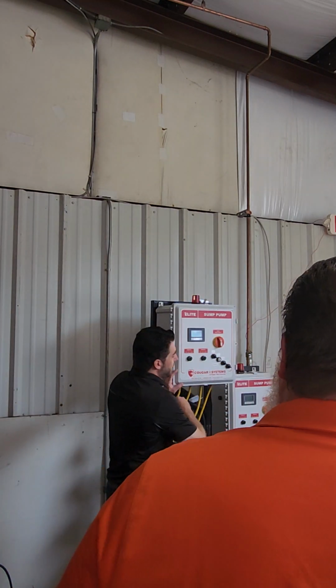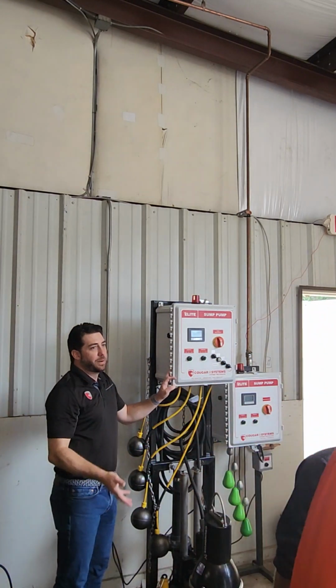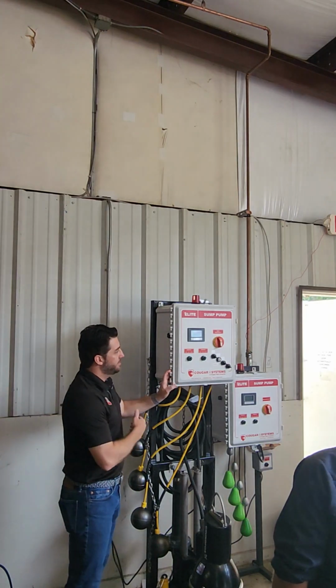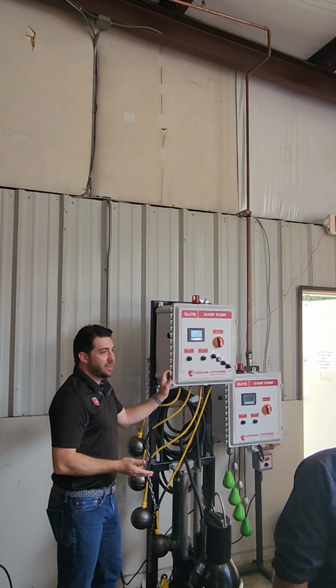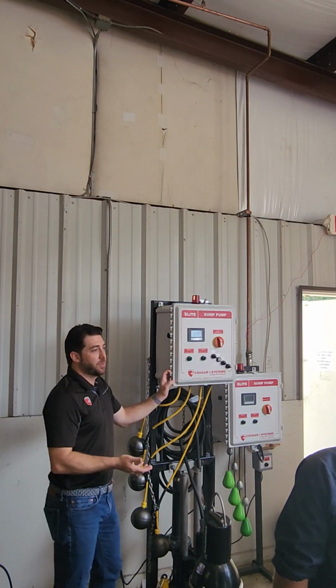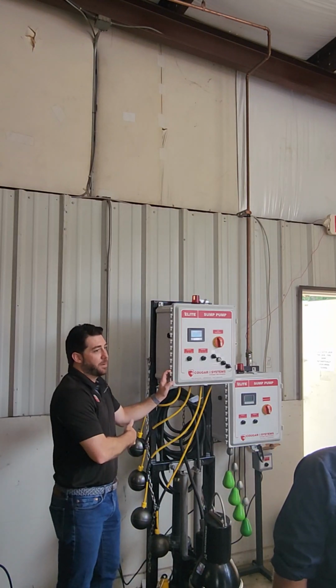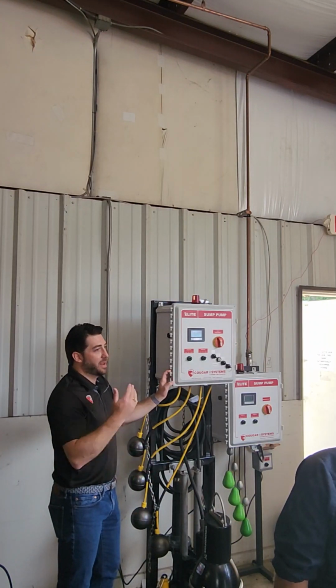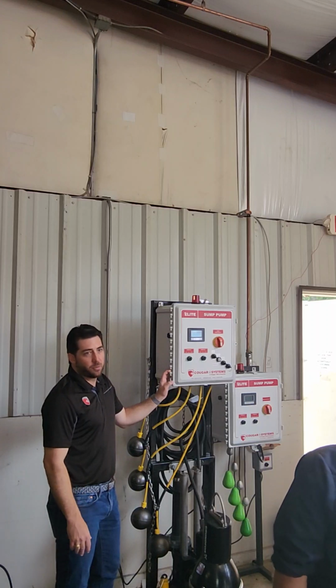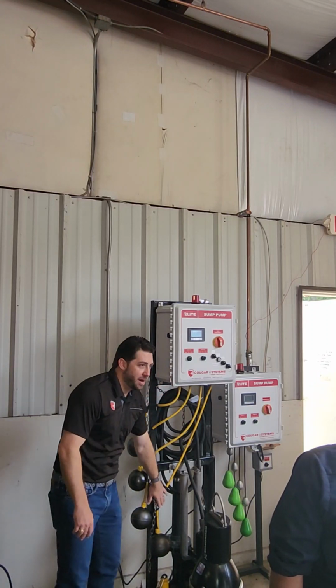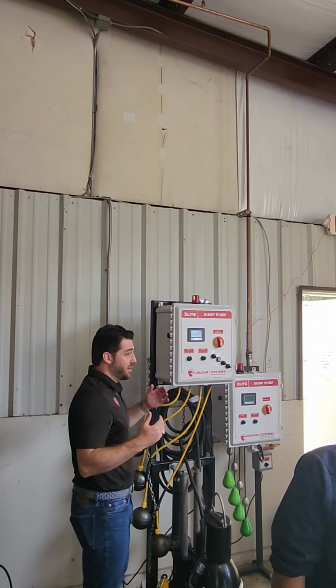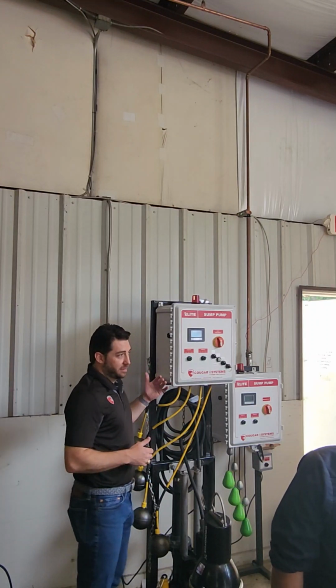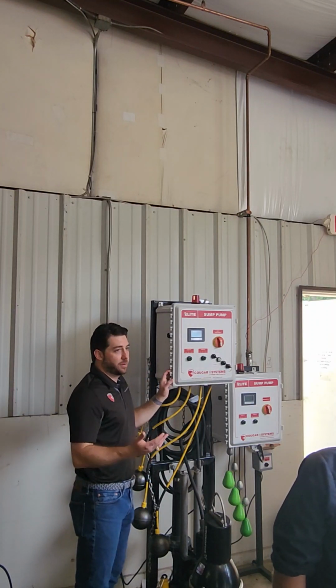So what we have over here is this max runtime alarm, and depending on what the normal pump down is in the pit, you can adjust that. But once it hits that runtime, it's going to alarm and tell you, hey, the pump's been running for an extended period. It doesn't shut the pump off, but it'll at least give you an alarm that, hey, something's going on in the pit this time. So that's going to protect you from that bottom float switch failing. Or if you just have a major upset event, it's going to let you know that, hey, this pump's been running for a long time.